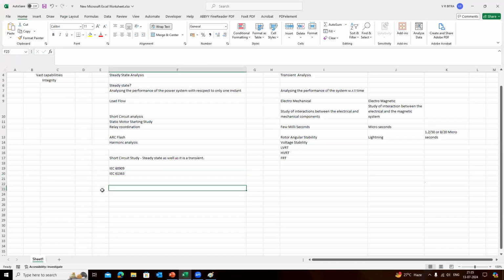In short circuit analysis, we are basically talking about two components: IK double dash, which is the initial symmetrical short circuit current, and IDC, which is the DC component of the current. The third one is the steady state current, which is IK. So when we perform short circuit studies, the different currents we find out are IK double dash, IDC, and IK.